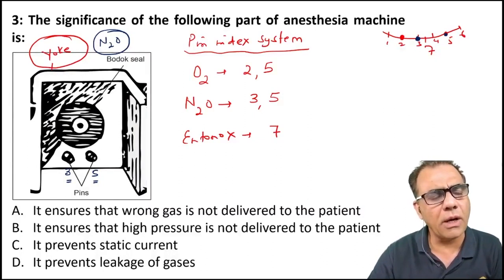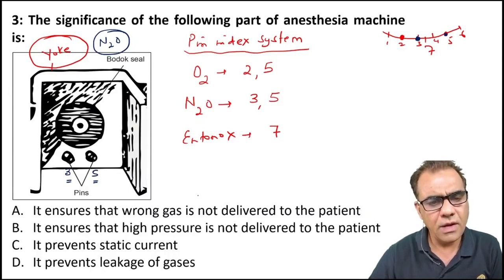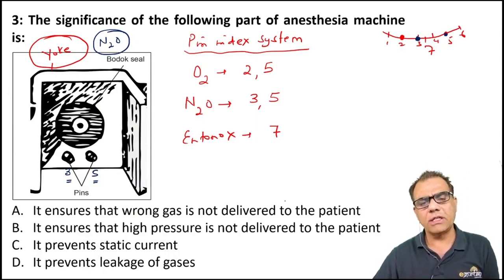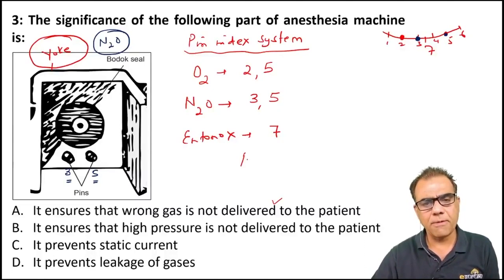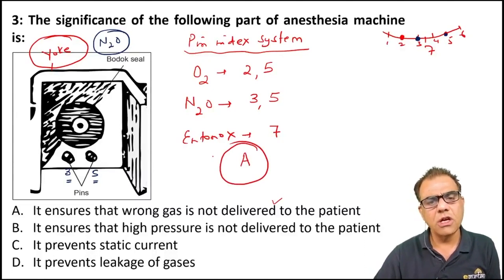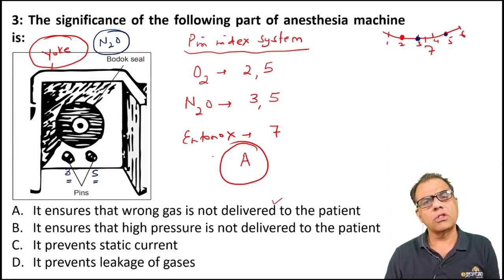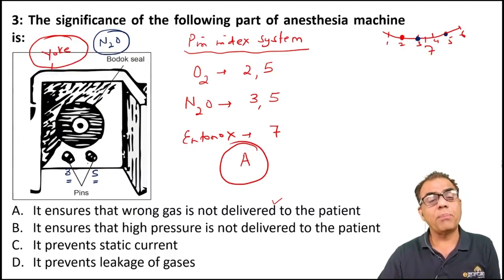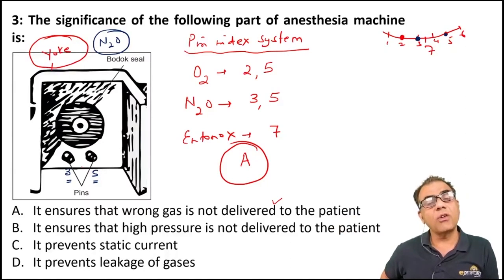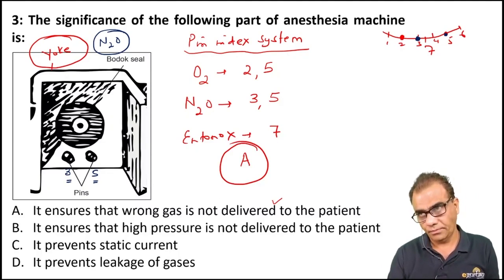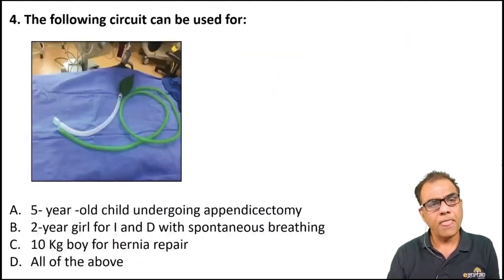The significance of this part of the anesthesia machine: it ensures that the wrong gas is not delivered to the patient. So the pin index system ensures that the wrong gas is not delivered to the patient because it can be catastrophic. By chance, if somebody places nitrous oxide in the place of oxygen and the patient receives 100% nitrous oxide, the patient is definitely going to die. So this is a very important protective mechanism to prevent the wrong fitting of cylinders.